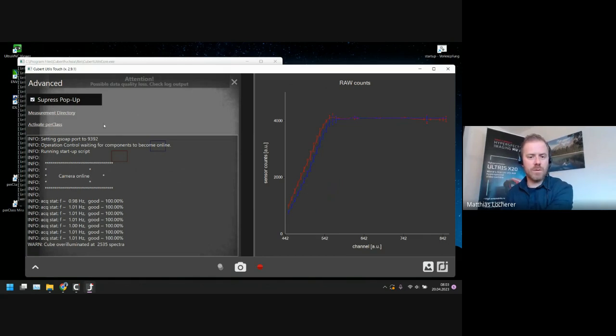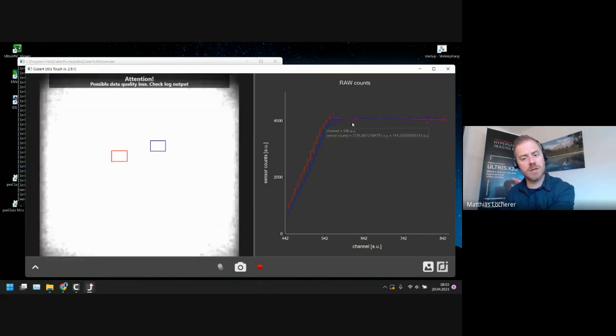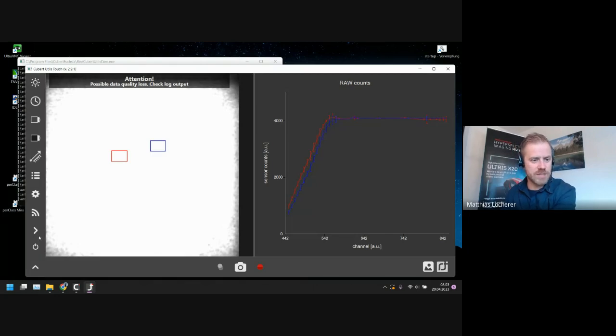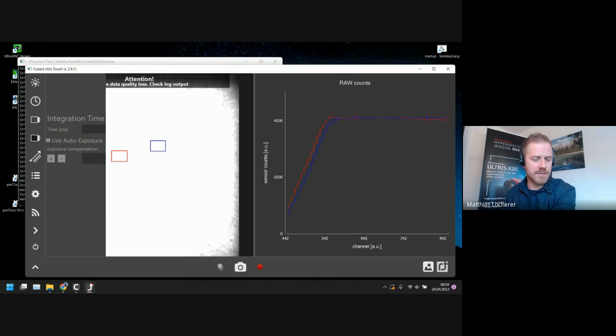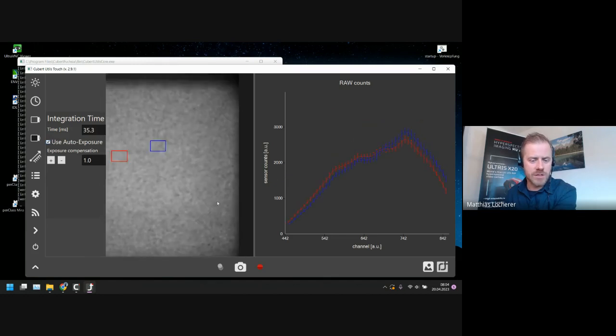So what we see now is that the data is totally oversaturated, meaning the integration time is way too high. So let's first have a quick view on the settings. We see here the integration time symbol, and the software starts with a default setting of 100 milliseconds. We don't need that. So let's use the auto exposure to find a much better value. And you see how it's decreasing, and also how the spectral response is going down and providing us with a not over-illuminated image. So I think 35 milliseconds is fine.